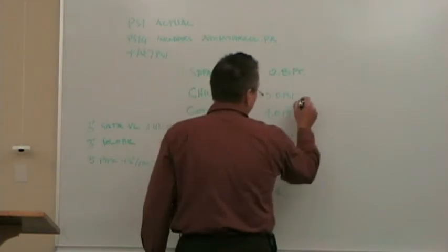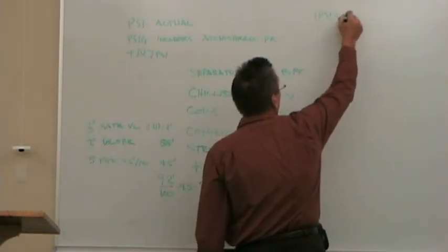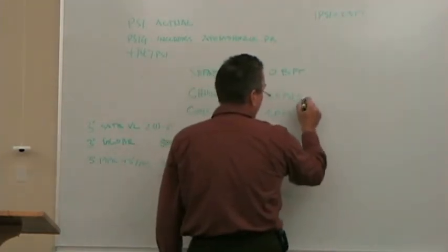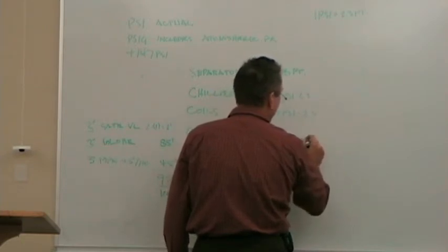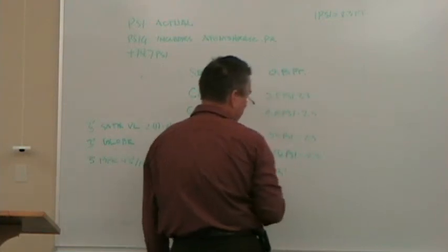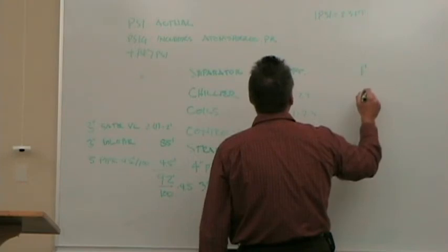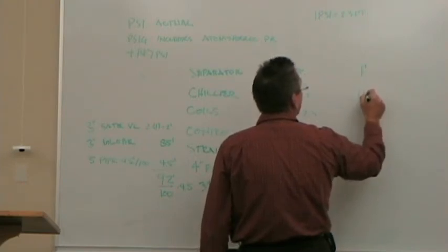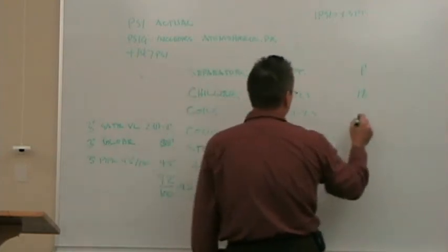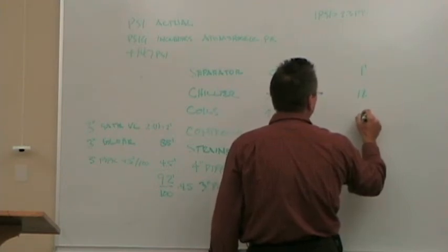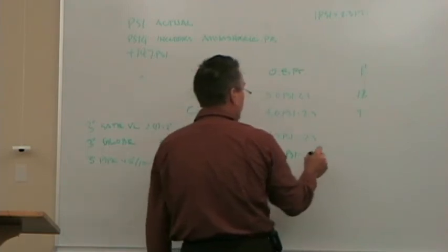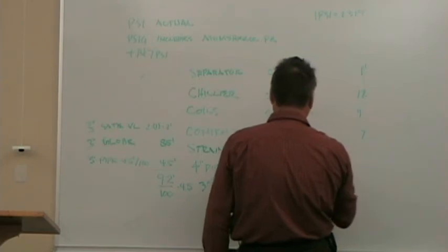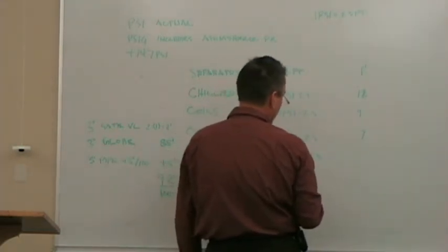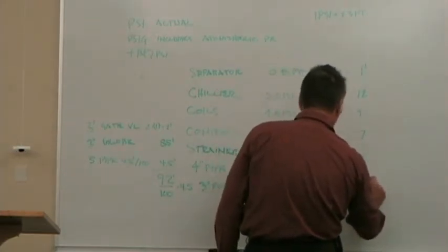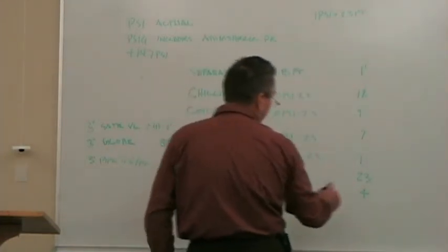Okay, so I get all these into the same units. 1 PSI is equal to 2.3 feet. So times 2.3, times 2.3, times 2.3. So I've got 1 foot out here, 11.5, and 11, round off to 12. 4 times 2.3 is 9.2. 3 times 2.3 is 7. And 0.6 times 2.3, 1.3. 123.4. Okay, what does that add up to?